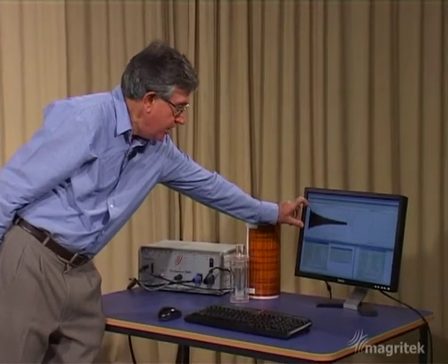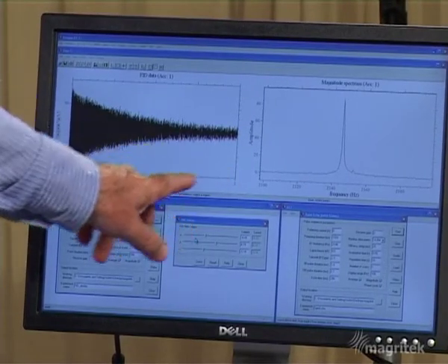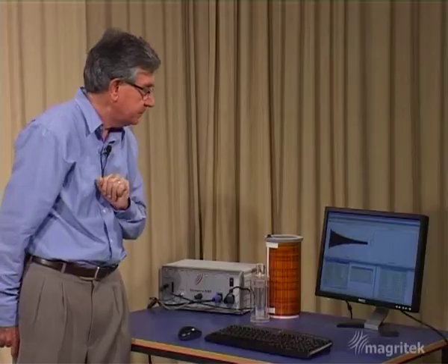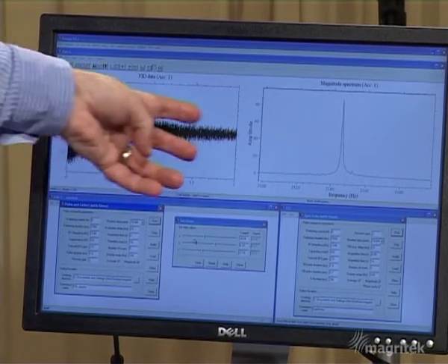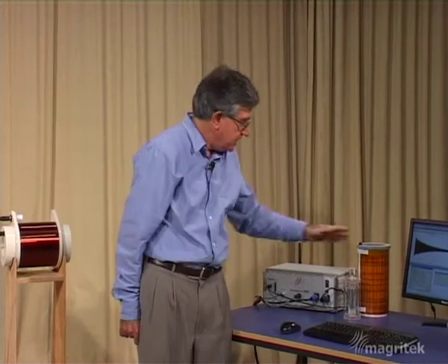Let's look at how this 90 degree pulse idea relates to our earlier free induction decay experiment. The free induction decay, or FID, spans from 0 to about 2 seconds. The 90 degree pulse happened right at the start, with a duration of about 1 millisecond — the time needed to turn the nuclear magnetization vectors through exactly 90 degrees. That FID is obtained with a nice homogeneous magnetic field, producing a long decay and a narrow spectrum. The shim coils used to produce that homogeneous field can also be used to make the field less homogeneous.